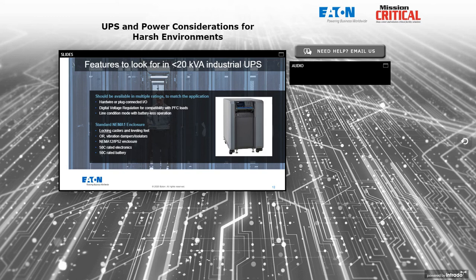So the kind of things to look for in an industrial UPS: the ability to hardwire it, of course, or plug connect, if that's what the client wants to do. As the UPSs get larger, they'll move to all hardwire input, output, and battery connections. But a plug-connected UPS can be found in the lower range, under 10 kVA specifically. Digital voltage regulation, the capability to handle power factor corrected loads beyond what the ferro does on its own, and line conditioning mode so the UPS can be used to clean the power without a battery. So if the client says, I don't want to invest in a battery, I'm not sure I need it yet, but I do need power conditioning, can I get a UPS that I have the option to add battery later, or that will still function if the battery's disconnected temporarily for whatever reason?